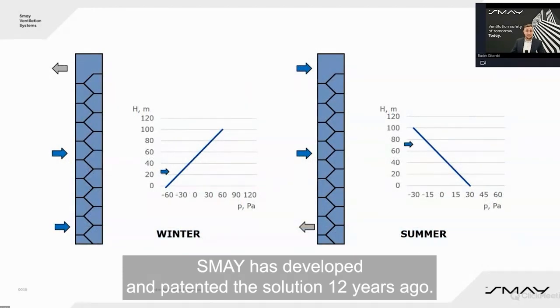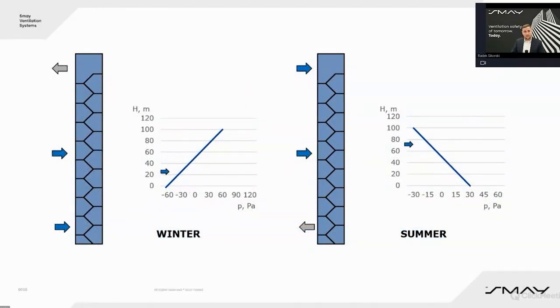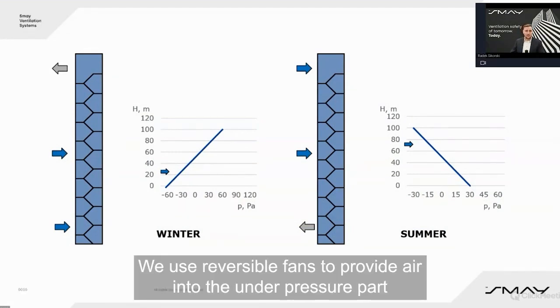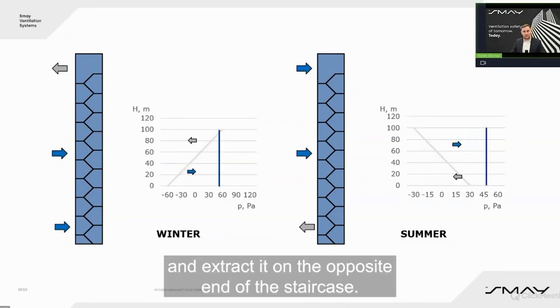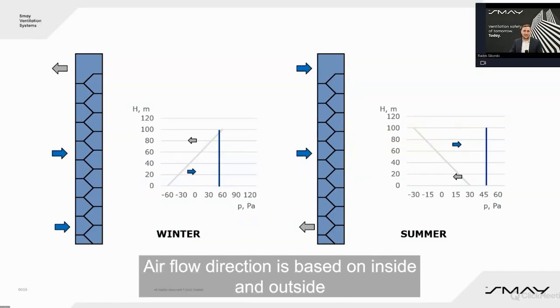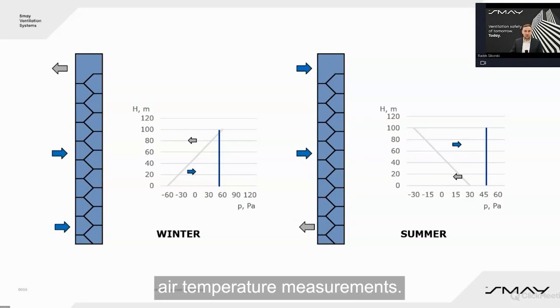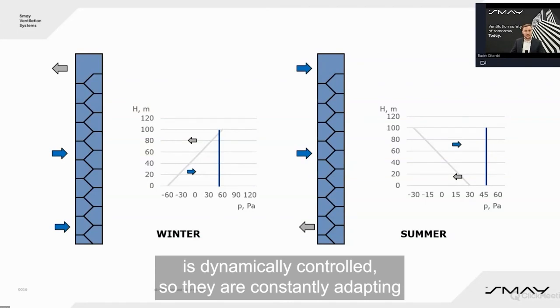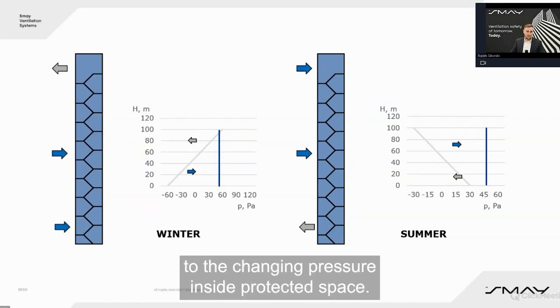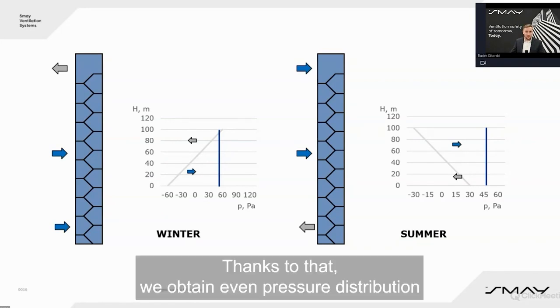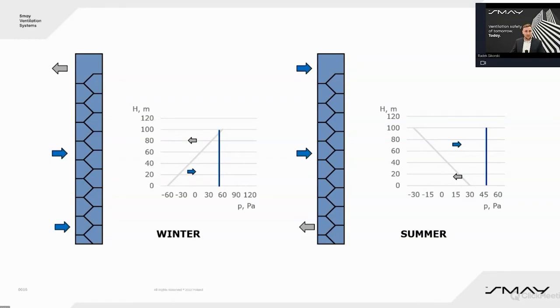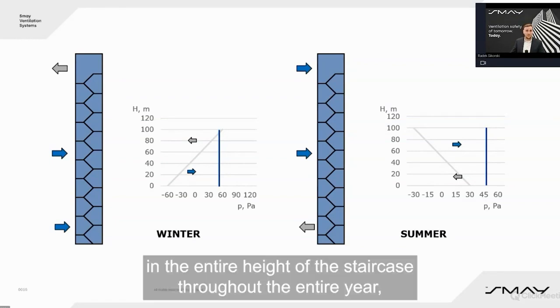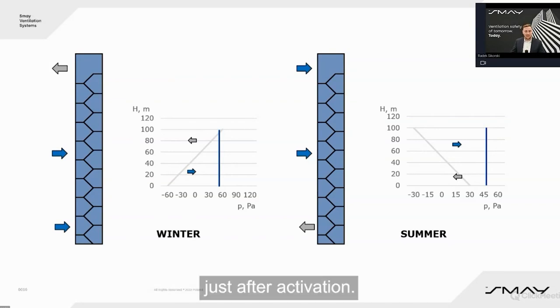SMAY developed and patented a solution twelve years ago. It is quite simple: reversible fans provide air into the underpressure part and extract it at the opposite end of the staircase. Airflow direction is based on inside and outside air temperature measurements. Each fan is dynamically controlled, constantly adapting to the changing pressure inside the protected space, giving us even pressure distribution across the entire height of the staircase throughout the entire year, just after activation.